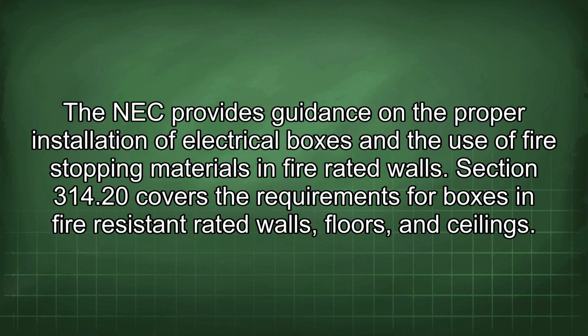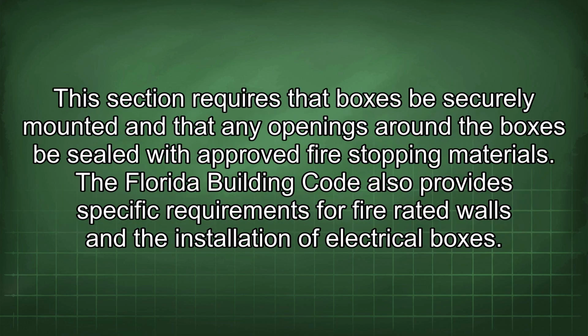Section 314.20 covers the requirements for boxes in fire-resistant rated walls, floors, and ceilings. This section requires that boxes be securely mounted and that any openings around the boxes be sealed with approved fire-stopping materials. The Florida Building Code also provides specific requirements for fire-rated walls and the installation of electrical boxes.